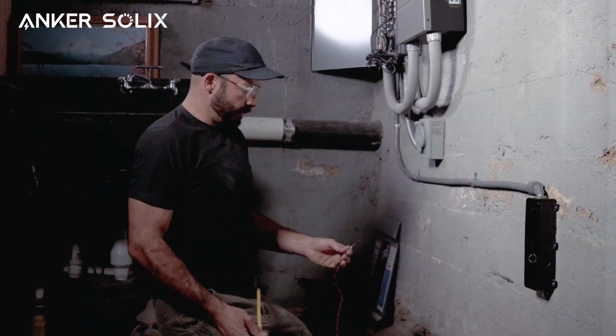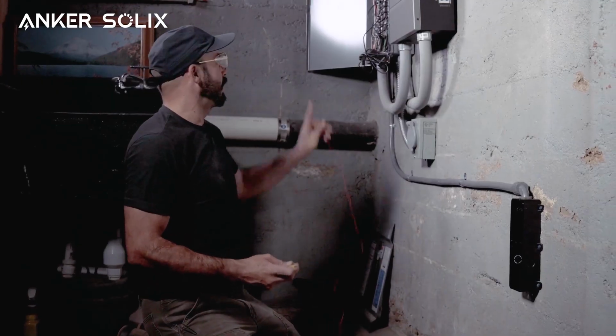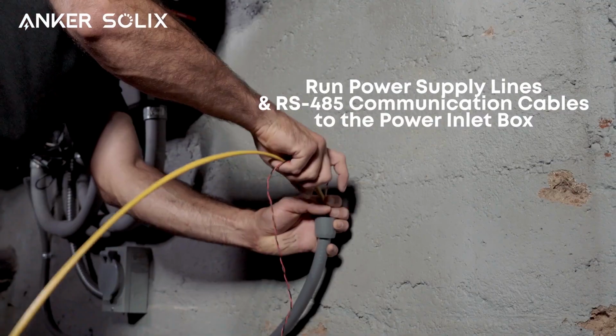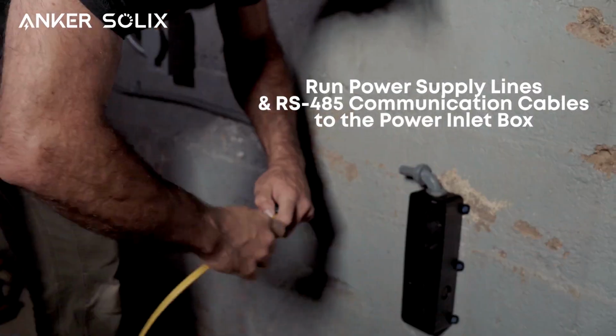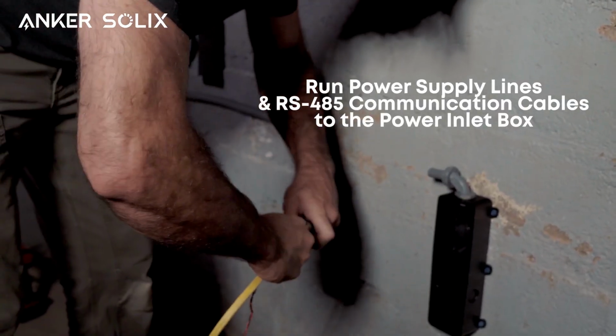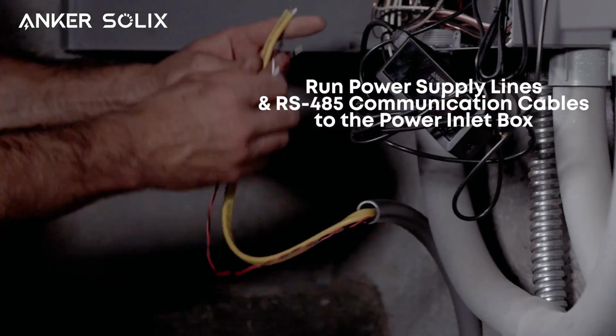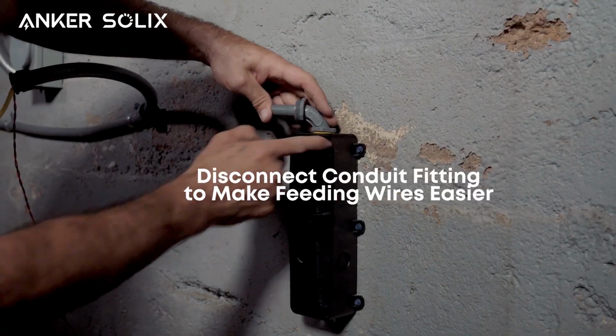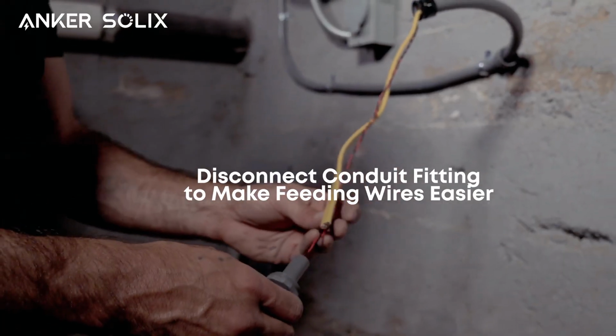With our conduit run, we can go ahead and run our power supply from our circuit breaker in the main breaker box, including our RS-485 communication cable, to the bidirectional inlet box. Sometimes it's easiest to disconnect the conduit from the fitting to get it started.